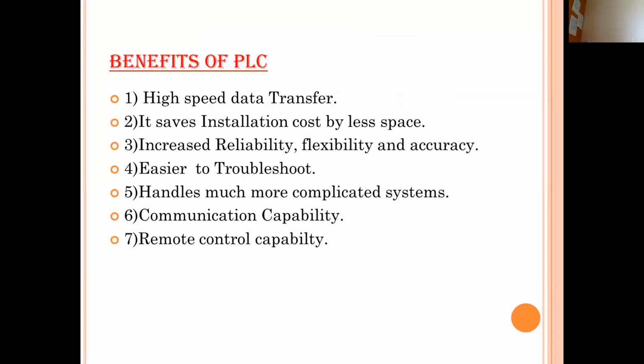So why are we going for the PLC? Actually, the PLC is used because it has high speed data transfer. The main thing is it saves the installation cost. If you go for relays, they will occupy more space, and debugging relays is a cumbersome job. If any fault occurs in the relay logic, it is a complex job to rectify it. With a PLC it is easier to troubleshoot, and it can handle much more complicated systems. Moreover, it has remote control capability, that is, it can work in a remote place, even in a hazardous place.